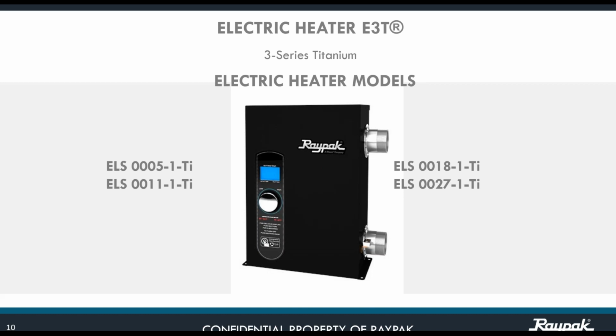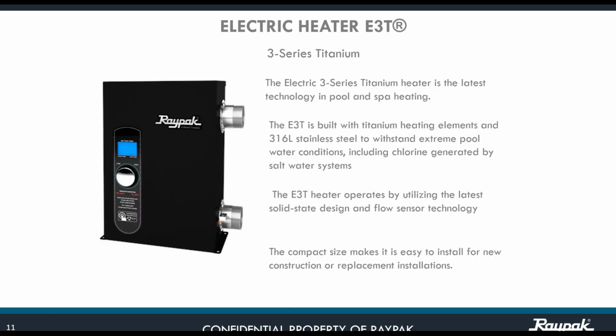There are 4 capacities in our new electrical heater: 5.5 kilowatts, 11 kilowatts, 18 kilowatts, and 27 kilowatts, where you can choose from. Completely revamped in design and functionality. It's really totally different from what you have seen in the past for our electrical heaters. It's a completely new internal casing, new material for the elements, and more advanced technology. We utilize titanium heating elements and 316 stainless steel that give the E3T the upper edge against the competition, especially for those applications on pool or spa where you are using chlorine generated by a salt system.